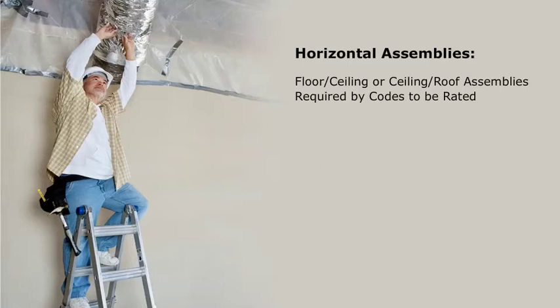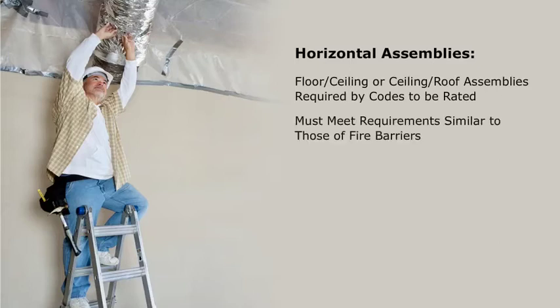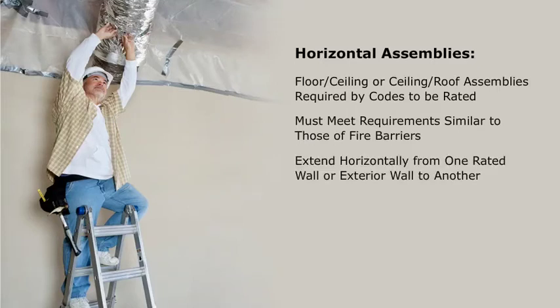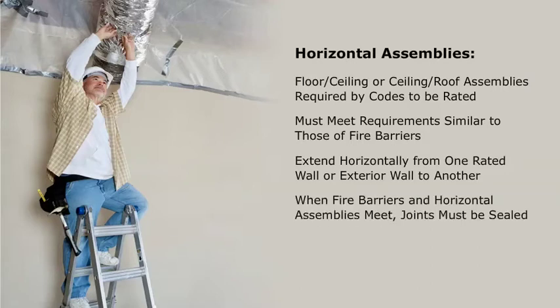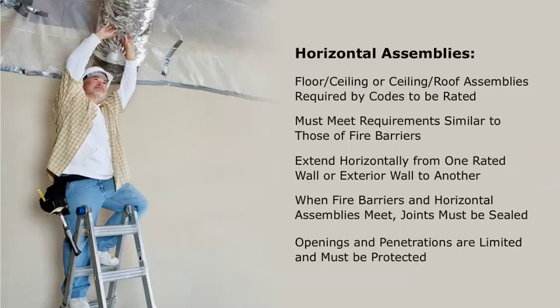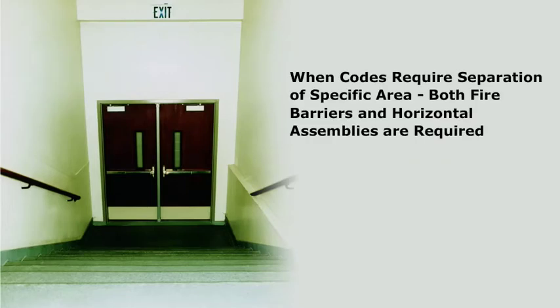Floor, ceiling, or roof assemblies required by the codes to be rated are referred to as horizontal assemblies. They serve the same function as fire barriers but are horizontal building elements. Horizontal assemblies must meet requirements similar to those of fire barriers, extending from one rated wall or exterior wall to another. Where fire barriers and horizontal assemblies meet, the joints must be sealed, and openings and penetrations are limited and must be protected.